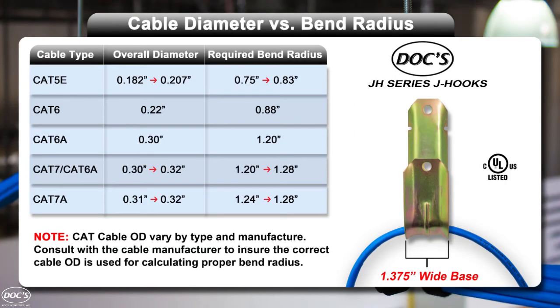In general, as cable has gone from Category 5 to 7 to accommodate higher speed data transmission, the minimum bend radius required to maintain cable geometry has increased. For instance, the minimum bend radius of a CAT-6A cable with an outer diameter of 0.3 inches should have a minimum bend radius of 1.2 inches.